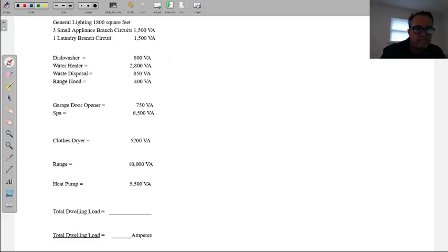So you said you don't include it, but since it's not four or more, what do you do? Do you still have to factor the 75%? So for this one here, no, we just add all these up. We would do 800 plus 2800 plus 850 plus 400, and that's it, 100% of its value. Okay, so it's only if it's four or more, then it's given the 75%. Exactly, 4 or more at 500 watts or more.